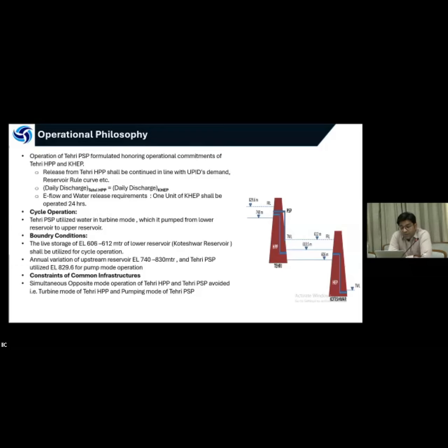In the cycle operation, Tehri PSP utilizes the water in turbine mode, which is pumped from the lower reservoir to the upper reservoir between the Tehri and Koteshwar at the level of 610.5 to 612. The boundary condition is that the live storage of 606 to 612 meter of the lower reservoir shall be utilized for cycle operation. Annual variation of the upstream reservoir is from the elevation of 740 to 830 meter, and the Tehri PSP is utilized at EL 829.6 for pump mode operation.